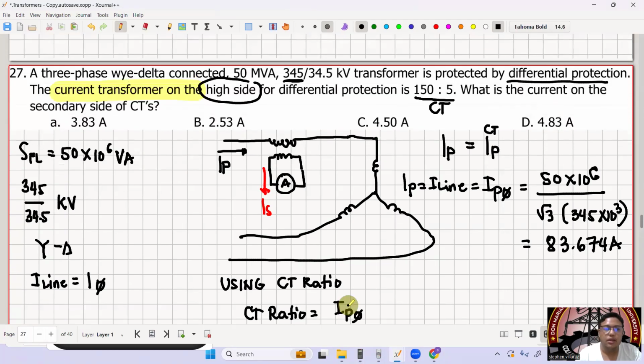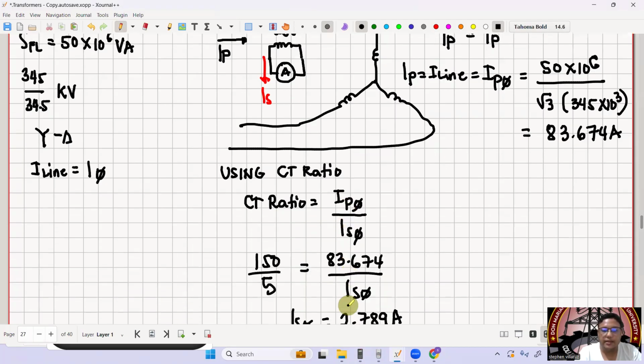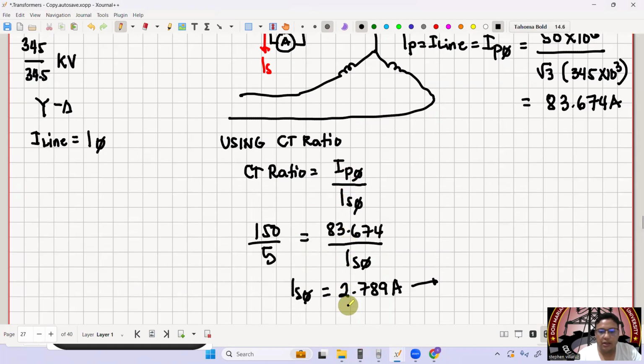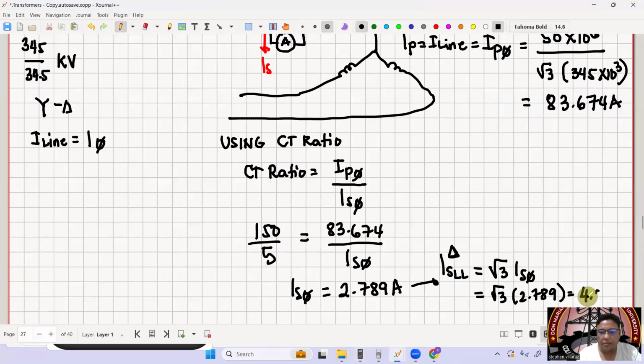Not yet, because what we want is the current on the secondary side, meaning line to line. Since we want ISLL, and since it's connected in delta on the secondary, this is now square root of 3 times IS per phase, which is square root of 3 times 2.789. Multiplied by square root of 3, this is now 4.83 amperes.